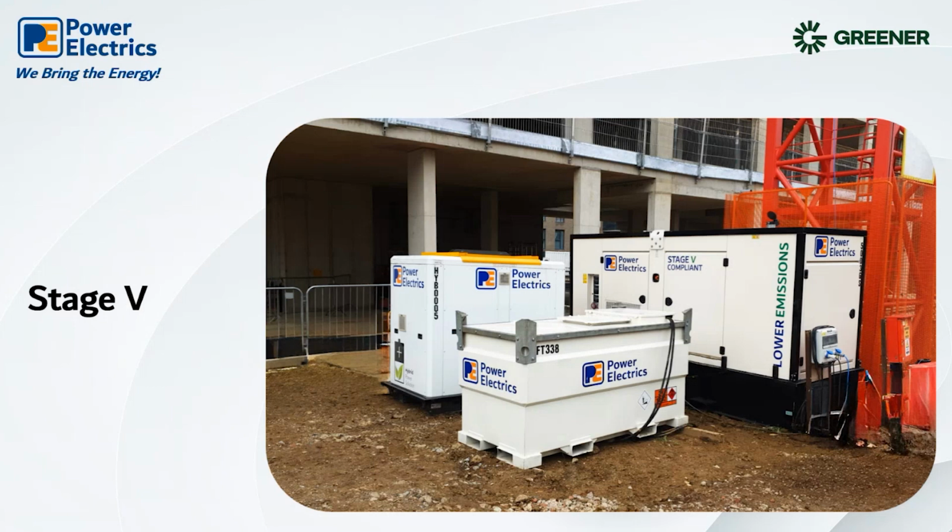So yeah, stage 5 really benefits from battery systems enabling, and we've worked very successfully with these around the London area, even from machines as small as 60 kVA stage 5s and batteries, enabling the heat cycles to be run through them and the emissions to be kept down low, and avoiding the faults of low loading on the generators.